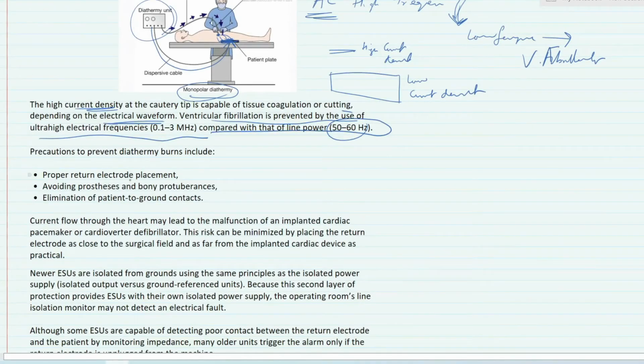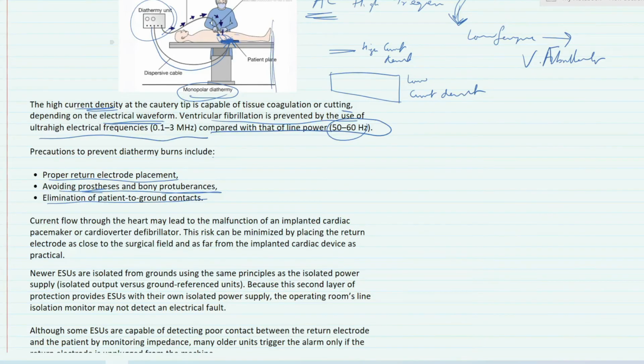The precautions that we can take to prevent diathermy burns: we have proper return electrode placement, and by proper, as I've already discussed, it should cover this whole area and avoid prosthesis and bony protuberance. Why? Because bone is a very bad conductor of electricity, right? So this is why bony protuberances should be avoided, and ideally it should be placed on an area which doesn't have bone or prosthesis. And elimination of patient to ground contacts: if the patient is grounded and there is a path of least resistance, then current would want to travel from the patient to the ground, right?